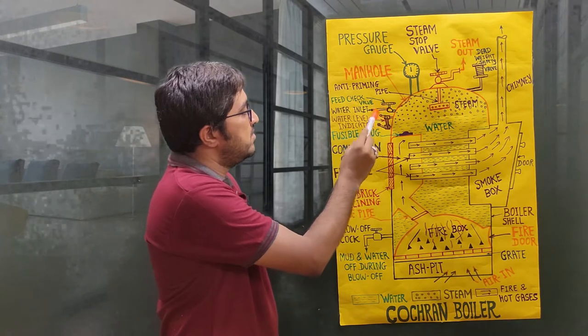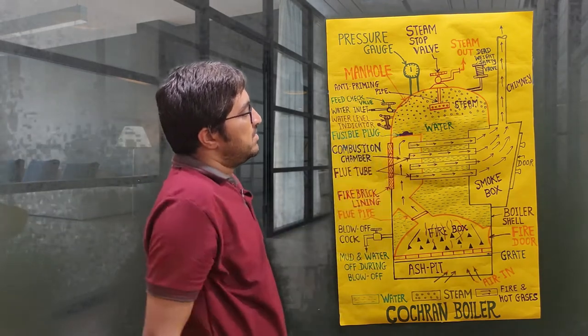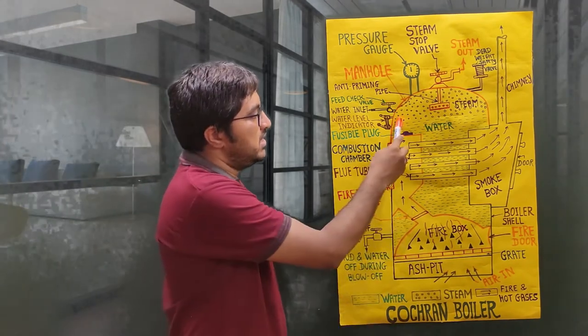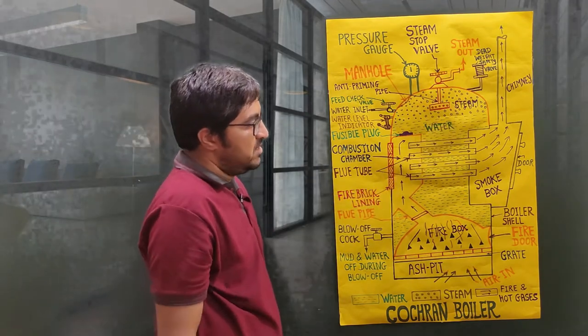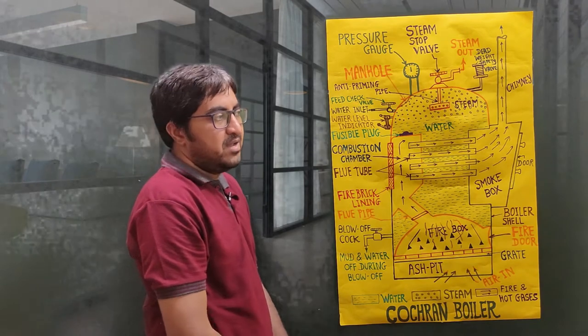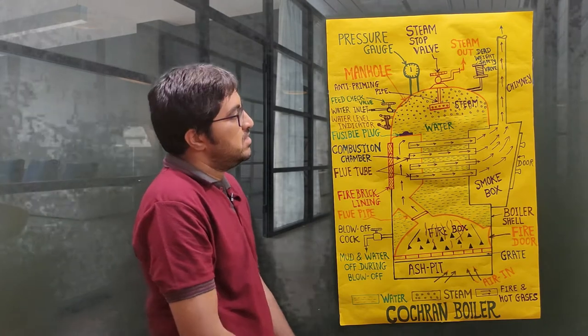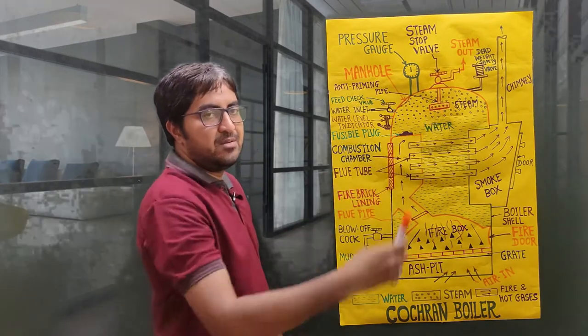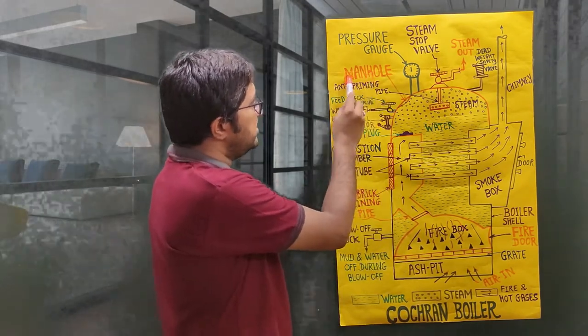The feed check valve feeds water into the shell. The anti-priming pipe removes water particles from the steam. Since steam is collected in the dome due to its lower density, sometimes water particles are suspended in the steam. If these water particles are supplied to the turbine, they will damage the turbine blades. The anti-priming pipe removes these water particles before the steam is supplied to the superheater and then the turbine.